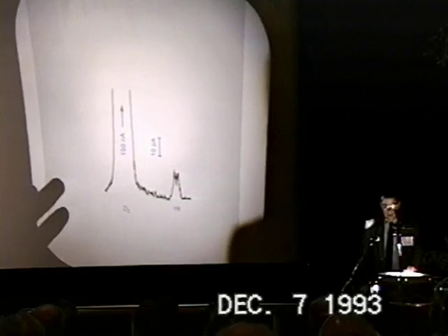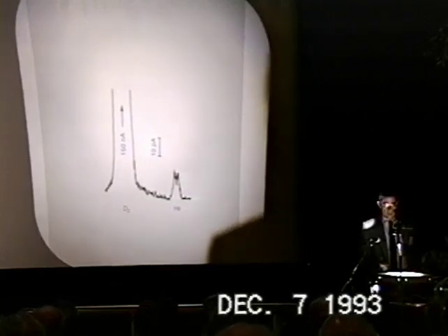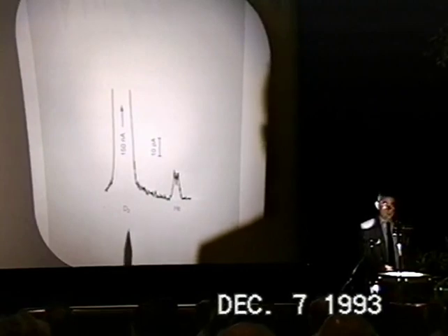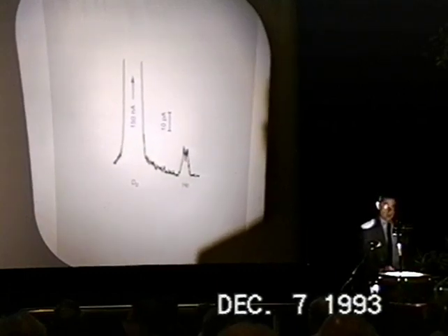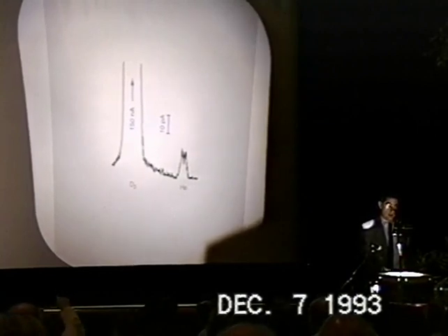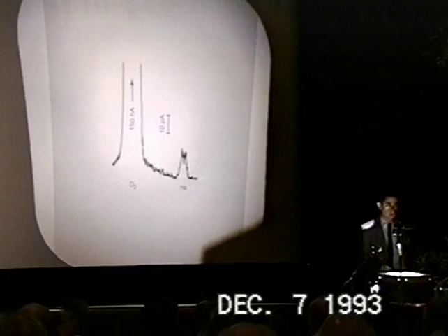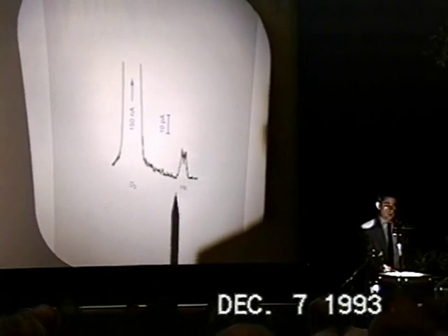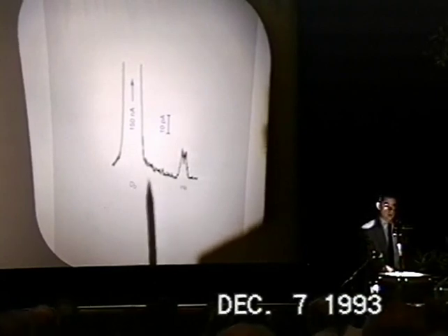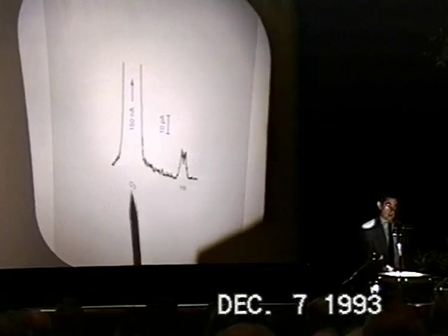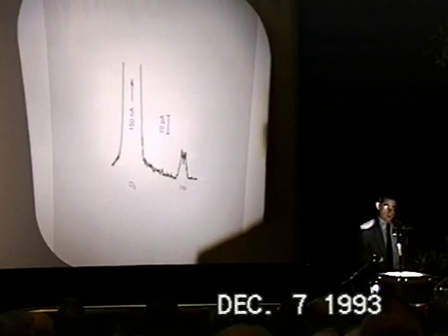What is really important in such a type of measurement is not the resolving power in itself, because basically what we are going to look at is probably a low amount of helium with a large amount of deuterium, or with any other mass near it, a low intensity signal near a high intensity signal. This is sometimes called the abundance sensitivity of the mass spectrometer. It means your capability to measure some low signal on the tail of the high intensity signal. This is a factor of 10,000 approximately.